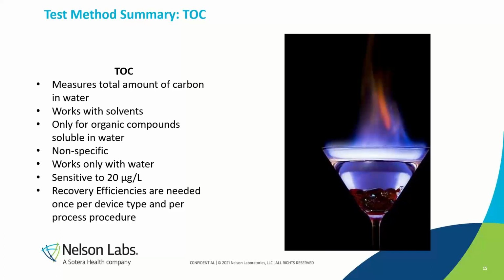And then again, there's not a slide for THC. So just as a reminder, THC is the flip side of TOC. THC is extracted in a non-polar solvent to detect primarily oils. At Nelson, it's a hexane-only extraction. An aliquot is put on a GC-FID for analysis. Great sensitivity, and the result again is a microgram per device. And a recovery efficiency is also needed for THC.